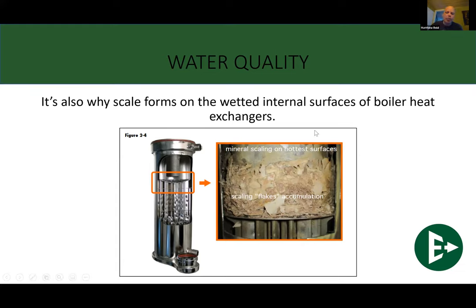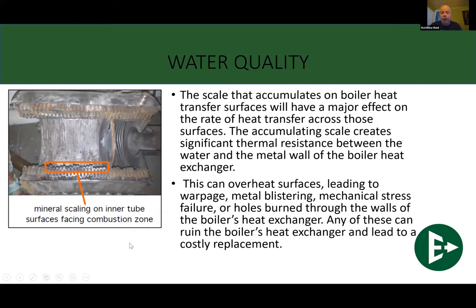If we have scale buildup, we don't have flow. If we don't have flow, we start cracking heat exchangers. And I'm not just picking on fire tube. This is a water tube heat exchanger that is completely plugged with scale. This is actually from a friend of mine. I can't remember the place where it is. But we did a cut apart of this heat exchanger, and we saw that we were only getting flow through about 8 of these tubes, through about a quarter of each tube. Everything else was completely plugged solid with scale and salt.